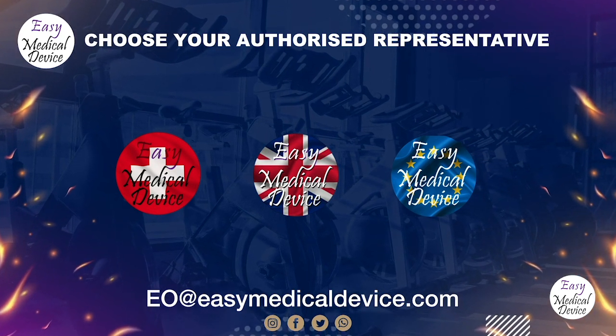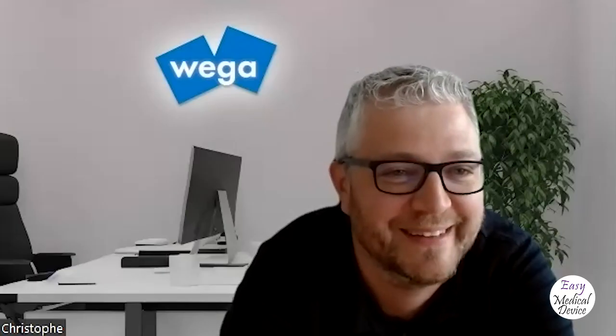Yeah, absolutely. There is a very old one that you might have heard from the FDA, from, I think, 2002 or something like that, called General Principles of Software Validation, which is a good source of information on what software validation can be about. A very broad standard that is used quite a lot in pharma and also in the medical device industry is called GAMP 5. You might have heard about that. Yeah, Good Automated Manufacturing Practice.